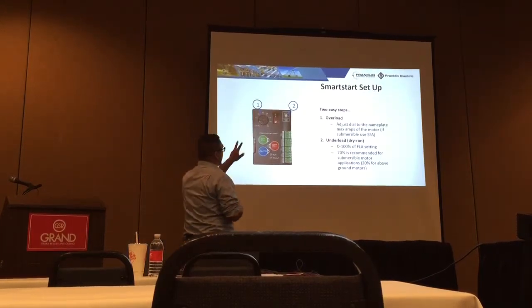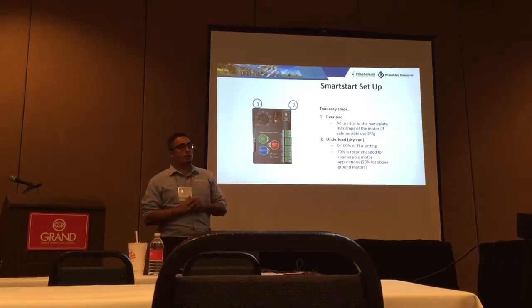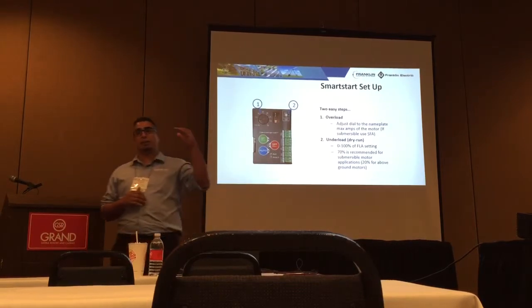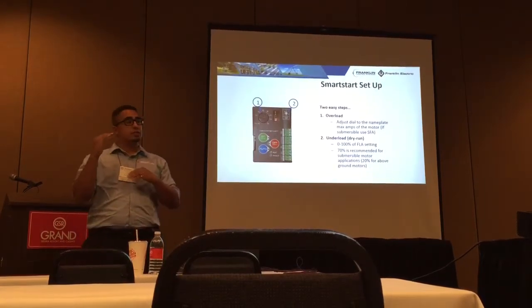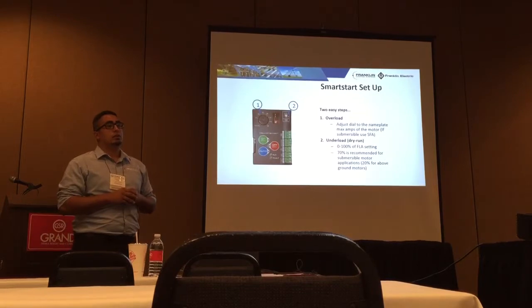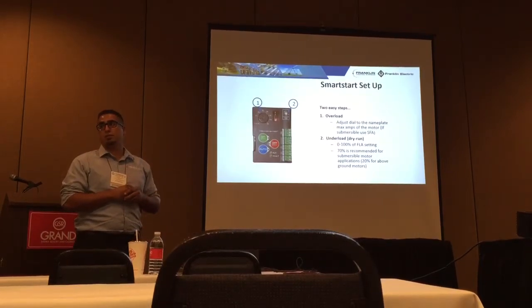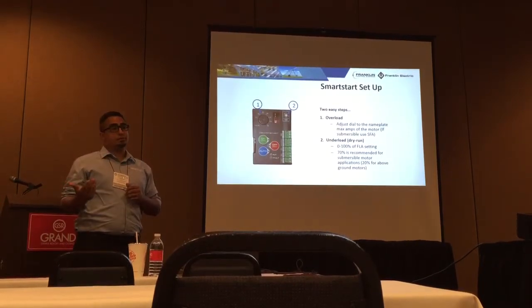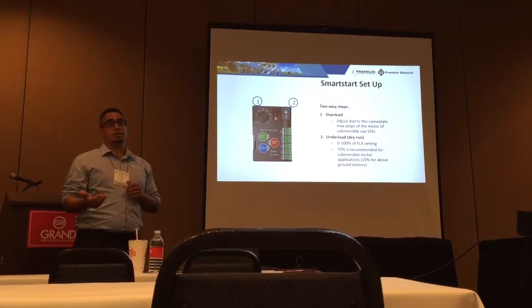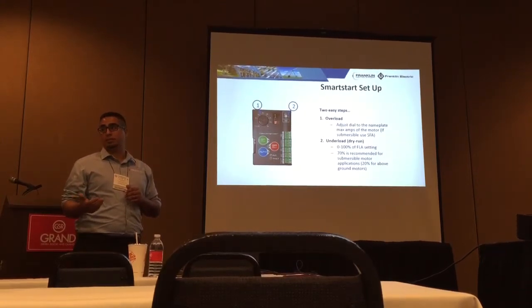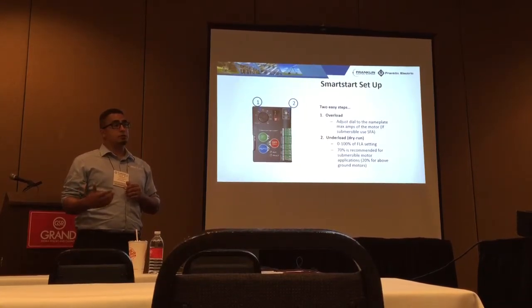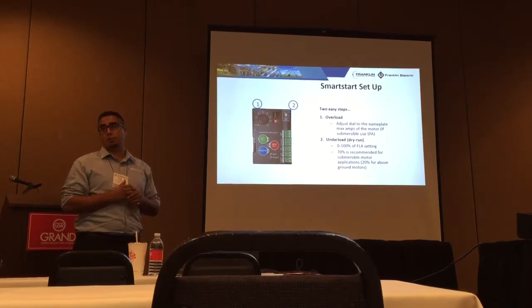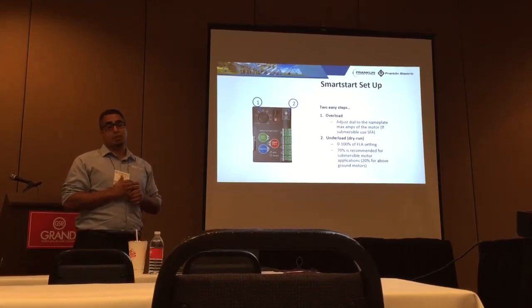So yeah, just 2 little dials on there, and right out of the box you have a high level cutout and a low level cutout because both ends are going to be protecting the motor. On these standard across the line overloads, you have to add some type of amperage relay, a CT of some sort. There's more work involved to actually trip a panel out front. Do we have any questions?